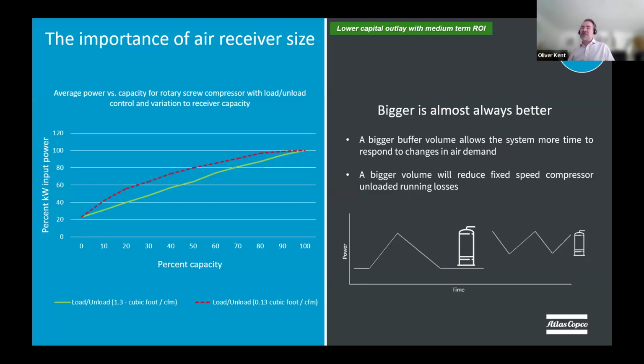Also, when it comes to distribution and your compressed air network, don't forget the volume of the air network. As a general rule, the larger the volume in terms of bufferage that you've got there, the better. So when it comes to air receiver sizing, the bigger the better. It's a simple rule. So why the bigger the better? It basically gives the compressed air controllers more time to react to what's happening in the compressed air system.